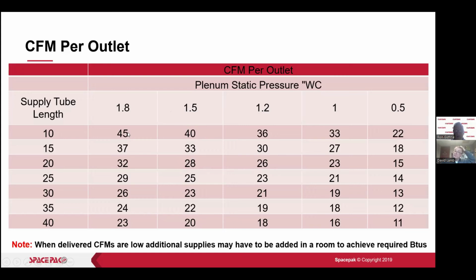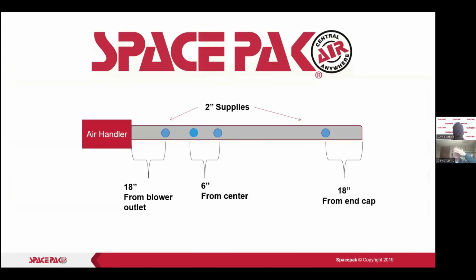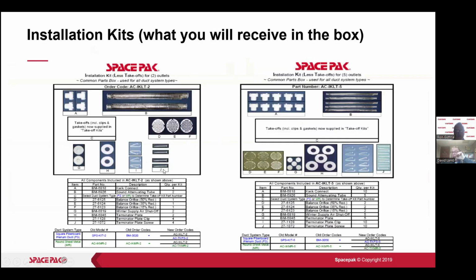If we go up in length, from 10 feet to 15 feet, we go from the 40 CFM that we want down to 33 CFM. If you get down to 22 or 23 CFM, you start losing the velocity out of the outlet and the aspiration effect as well.